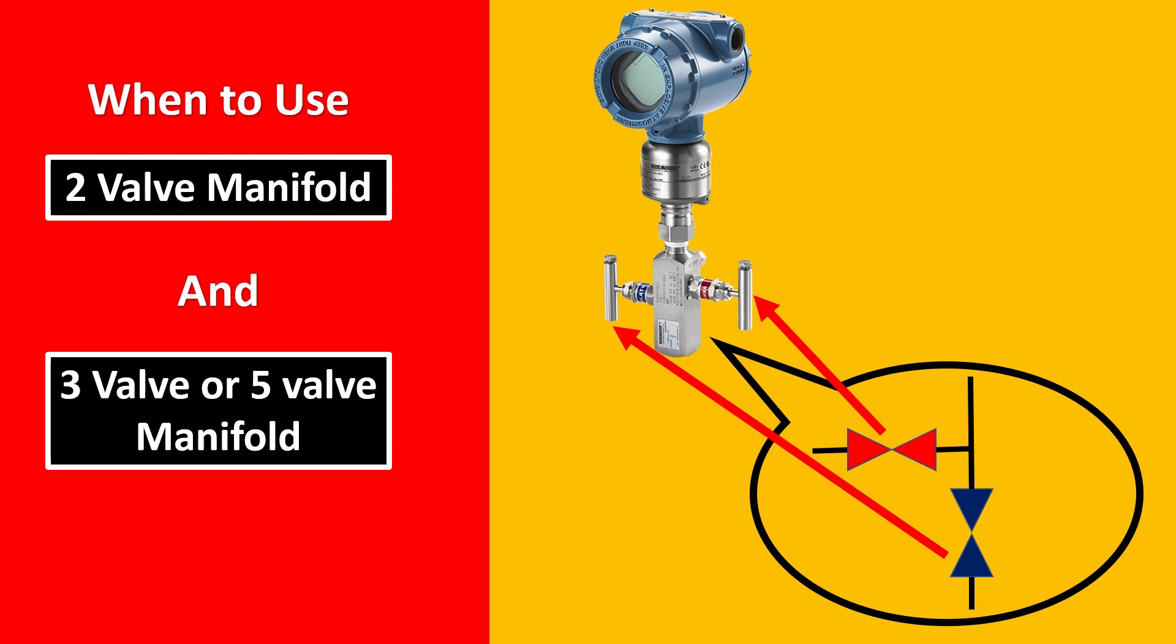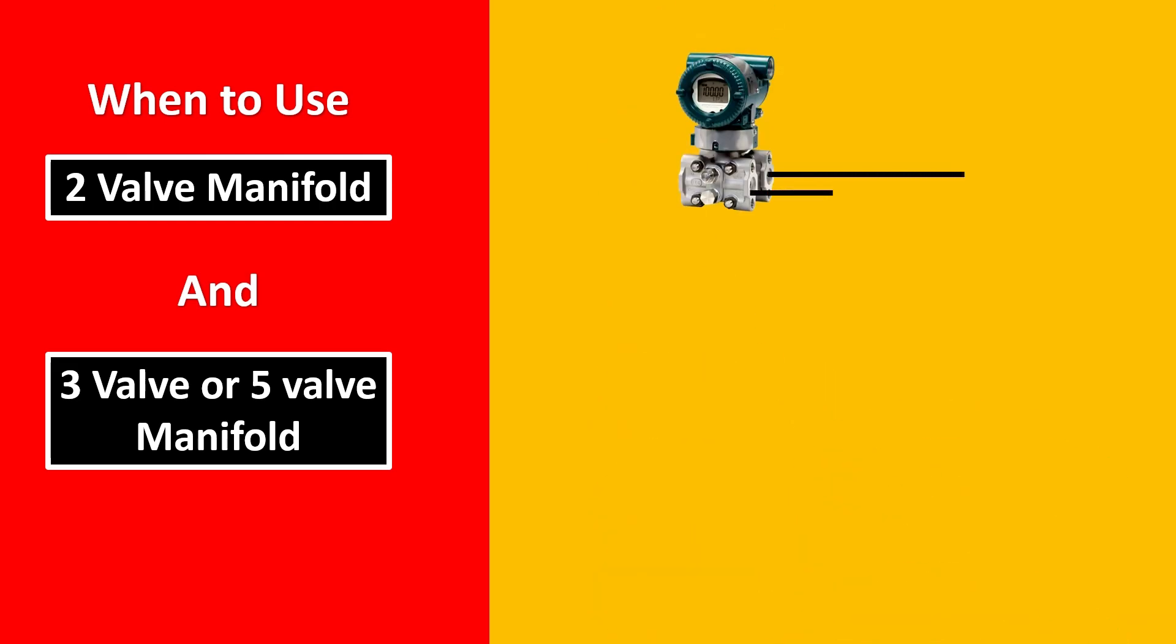Now second is when you have 3 valve manifold. Now 3 valve manifold here is used for DP transmitters. You will have these 2 tappings or these 2 valves is open and this one is closed. But when you want to remove the transmitter out, you would have to close these 2 things. You would have to open the equalization valve. And if you want to vent or drain it, then you might have to use maybe the transmitter vent or drain to release it out either to the atmosphere or to a closed drain system.